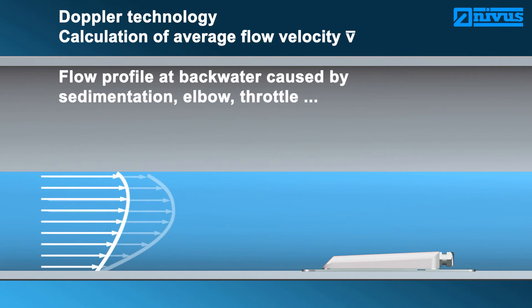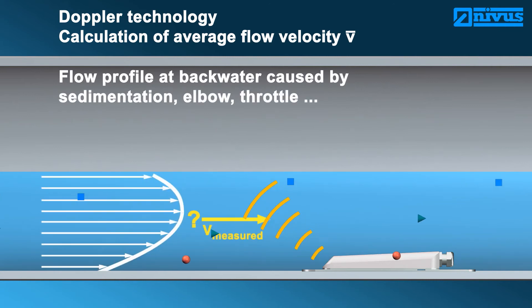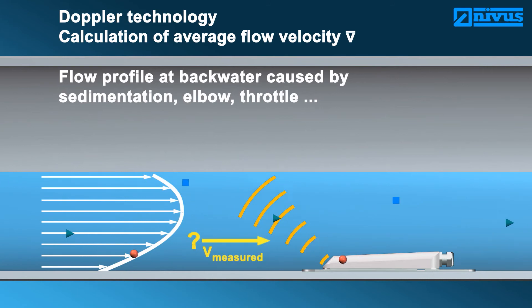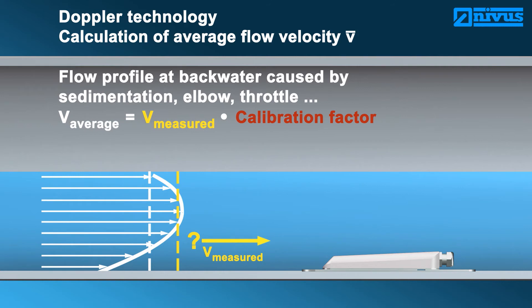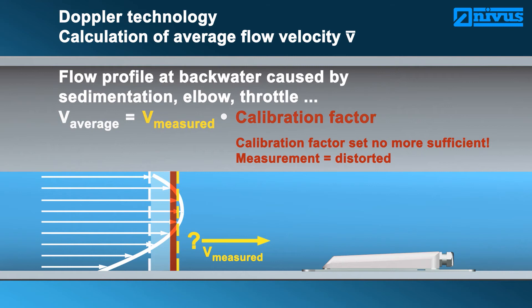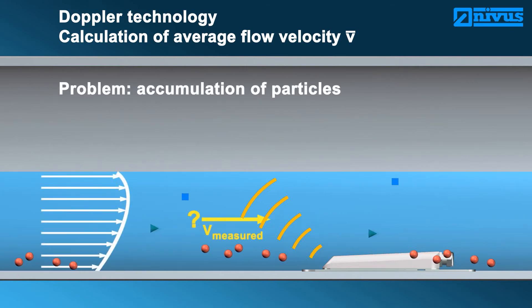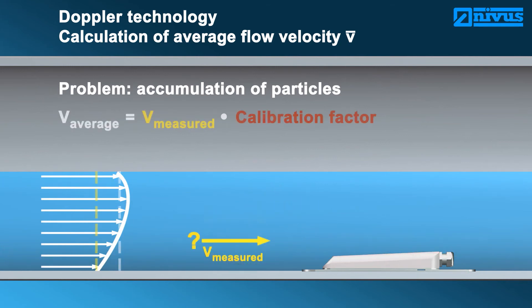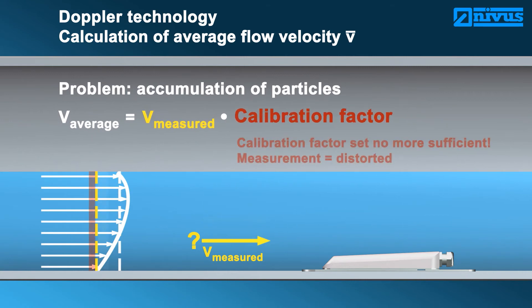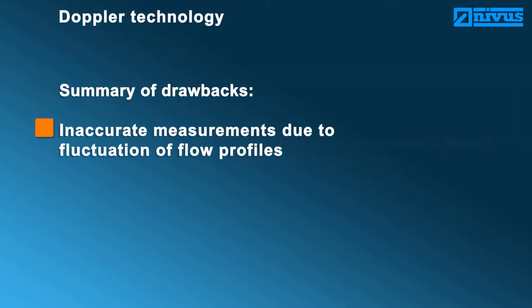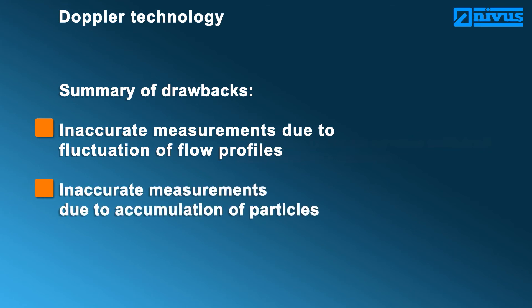The flow conditions will change even in case of backwater formation caused by sedimentation, elbows, or throttle equipment. The original calibration factor is no longer valid, and the measurement results are faulty. Accumulation of particles generates a stronger measurement signal and hence is determined by the sensor as the measurement spot. A local variation therefore creates a distorted reading which varies from the calibration. The shortcomings of Doppler measurement systems in brief: faulty results at varying flow profiles, faulty results in case of changing particle concentration, and no permanent calibration possible.